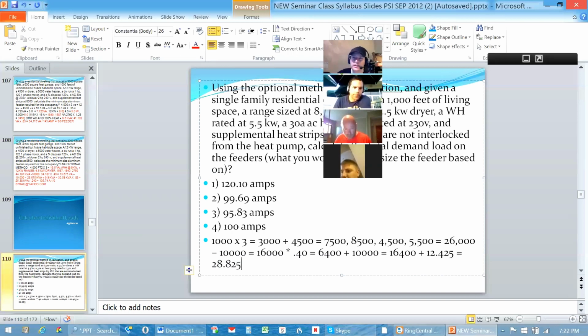No, that's what I was telling you: put yourself a note at the bottom of note 4 in the left-hand column to make sure that you separate those two steps. Section B is done as a derate block, and after the derating, that 16,400 is our connected load for sections B1 through 4. Then we add to that whatever we choose out of the 1 out of 6 from the C section. The 12,425 comes out of part C3, and it's 100% of whichever number we pick. There's no derating factor. It's not derated by 40% or anything.